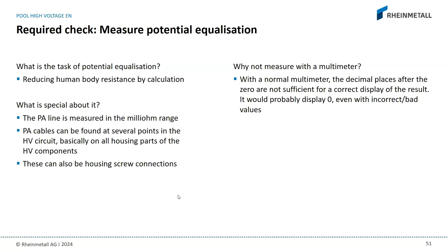And if the housing is not screwed one by one, we need to put, like, a ground cable from the outside of the housing from one point to the other to ensure that we don't have a different potential here. A different potential means plus and minus, because one potential is higher and one is lower. And if I have a potential difference, it means I have a current running through.